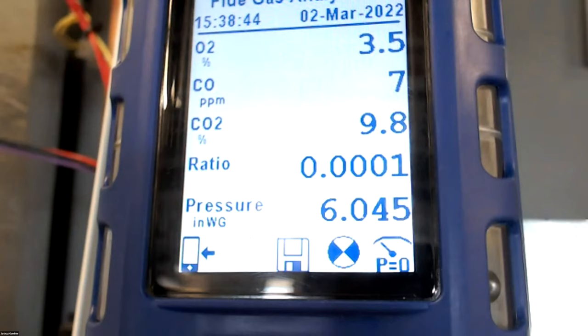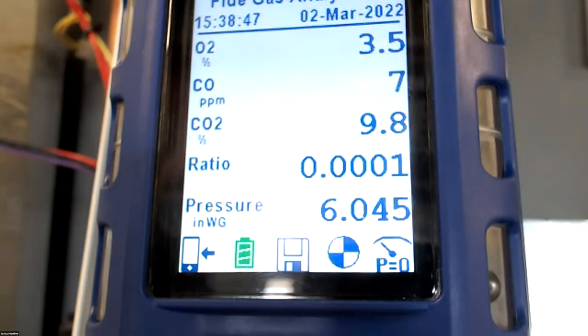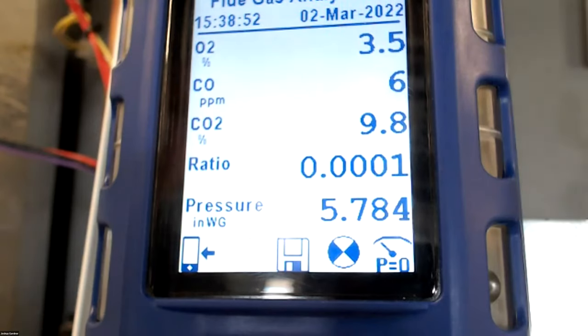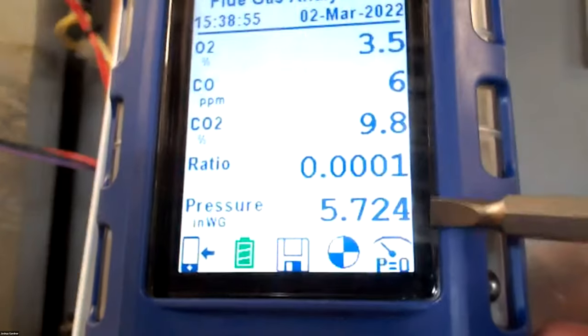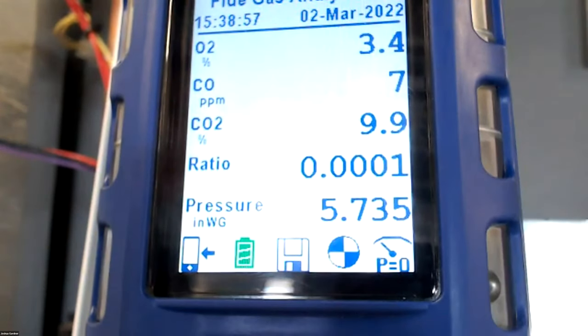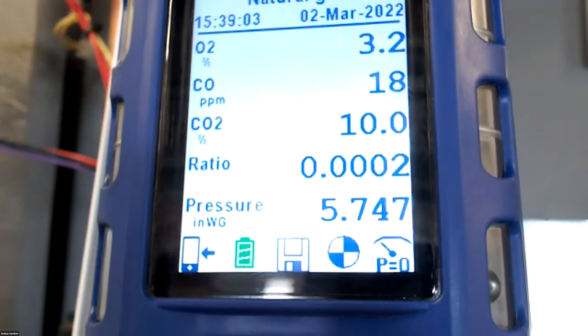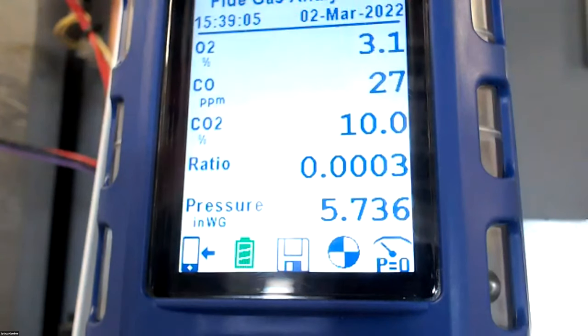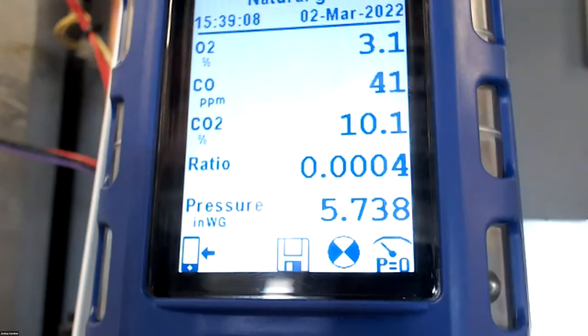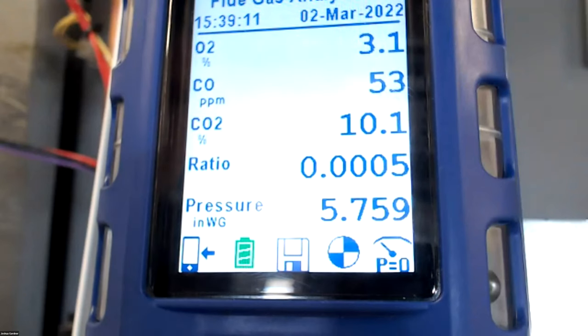But what I'm going to do is bring this up into high fire. So I'm using the right arrow and bringing the level up to 50%. I'm watching my gas pressure, seeing where I'm dropping, seeing if I'm seeing fluctuations. This is a good time to diagnose if I've got the volume and if my regulators are working properly. Keep the manometer on there. A lot of guys tend to check the gas pressure and want to take the manometer off immediately, but leave it right on there as you're doing the setup, so we can see the drop as well. 80%.